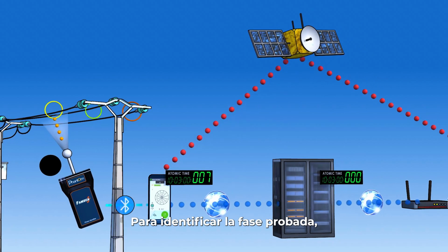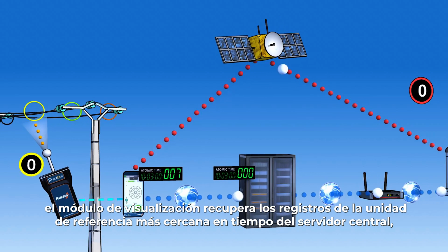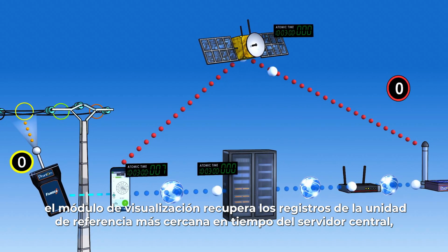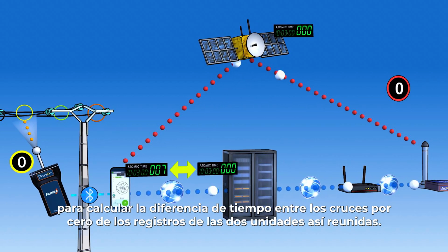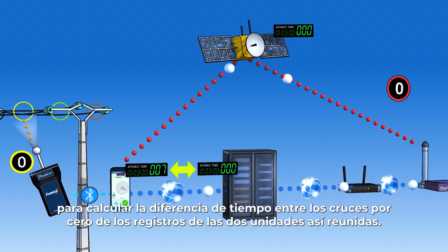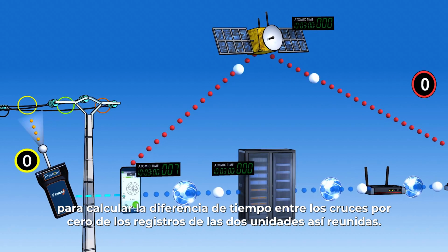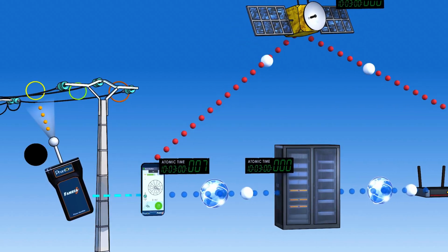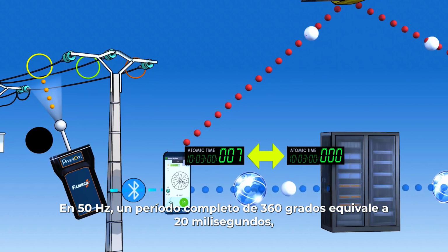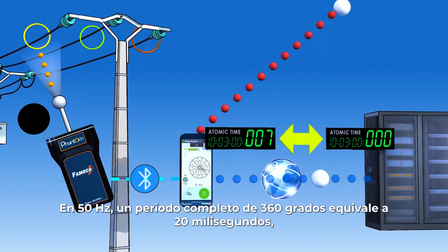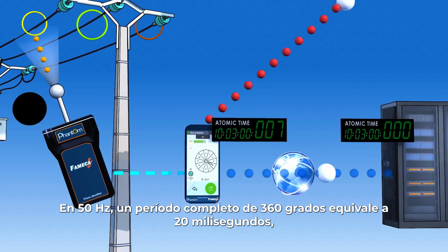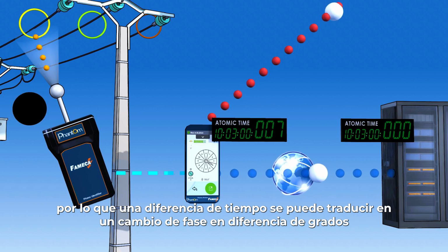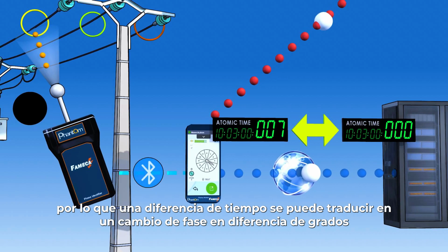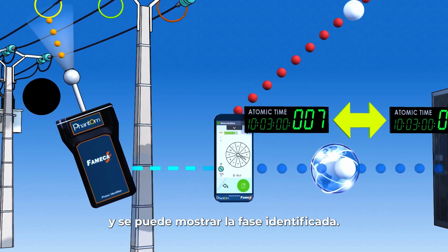To identify the phase tested, the display module retrieves the closest reference unit records from the central server to calculate the time difference between the zero crossings of the records of the two units thus brought together. In 50 Hz, a full 360-degree period is 20 milliseconds, so a time difference can be translated into a phase shift in degree difference, and the identified phase can be displayed.